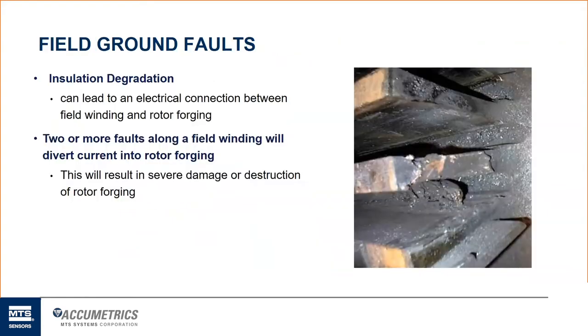So here's an example of a field ground fault. Basically what I was talking about, the insulation degradation can lead to that electrical connection between the windings themselves and the rotor forging. Traditional wisdom has always been, well, if you have one ground fault, it's not that bad because you're not diverting current through one connection. If you have a second ground fault, as the next bullet point says, two or more faults will then cause all of your current to divert directly into the rotor forging itself, causing this kind of damage you see over to the right, where it's burned in and it has to then go out of service and be repaired. It can lead to a lot of destruction and damage.